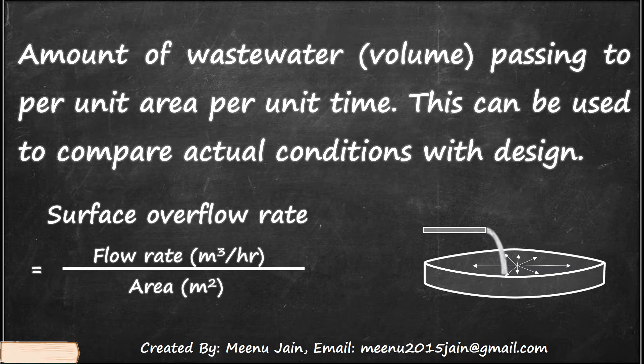Surface overflow rate is the amount of wastewater passing through per unit area per unit time. This can be used to compare actual conditions with design. The formula for surface overflow rate is inlet flow rate per unit area.